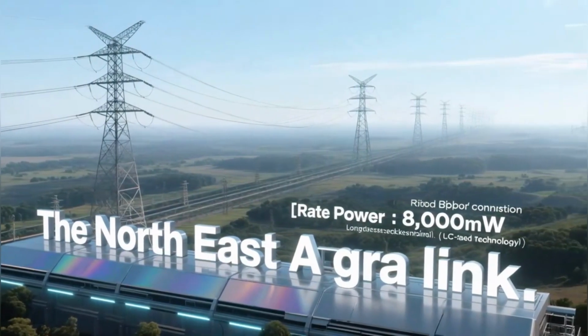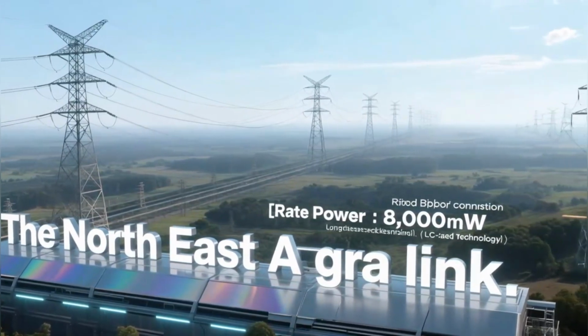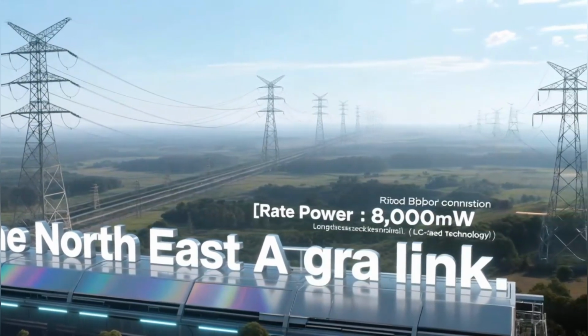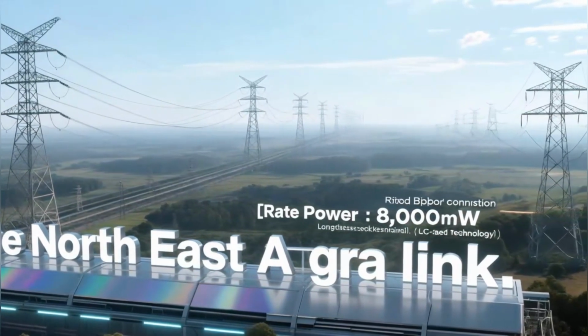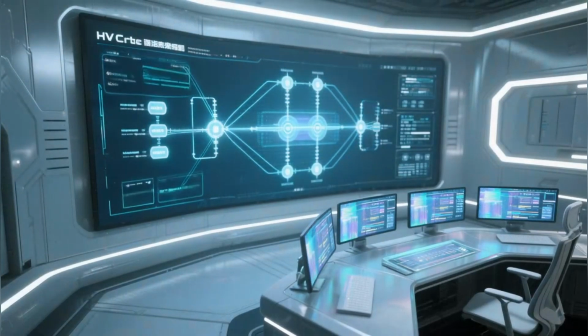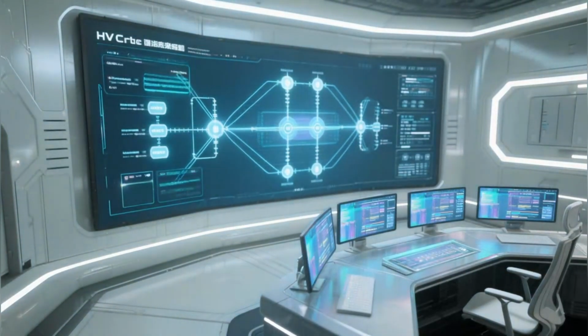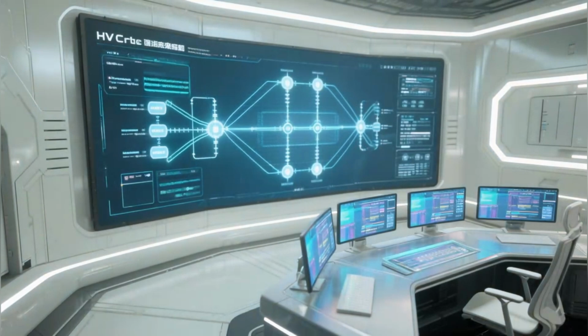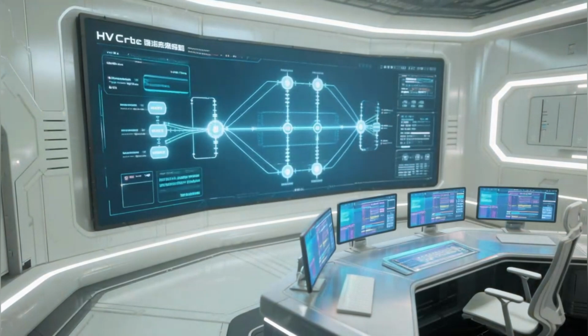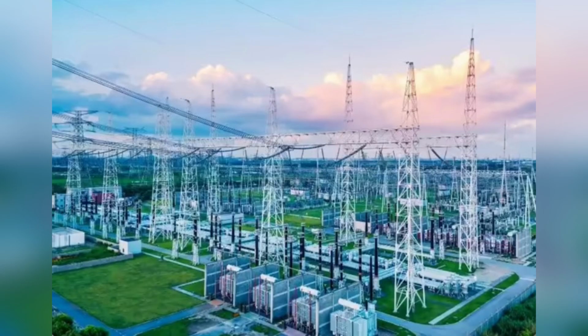The North-East Agra link. Rated power 8,000 MW, bipolar configuration, long distance overhead transmission, LCC-based technology. At the time, this was among the highest capacity HVDC systems globally. This is what makes the project truly unique. Traditional HVDC systems are point-to-point, one rectifier, one inverter, but this project introduced a multi-terminal configuration, meaning more than 2 converter stations connected to the same DC system.